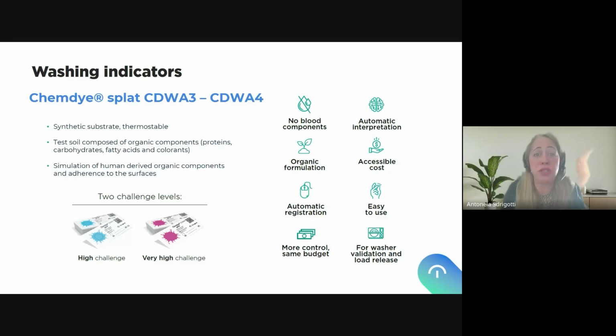The composition of this test soil is of course according to the ISO standard for organic residues, as well as the difficulty or adherence of these human residues on the surfaces of instruments. So in the end, this test soil simulates what happens with the real human residues that can remain on the instruments. We have two different types of challenges because there are many manufacturers worldwide that work with different parameters. Most of the validation processes and the intended use of washers are very strict and very high. So this is why we always recommend using the high challenge indicator, the pink one.